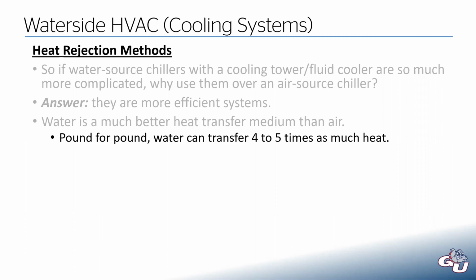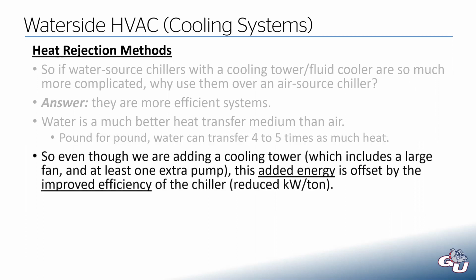Pound for pound, it's about 4 to 5 times as much heat that you can transfer through water as opposed to through air. So we're adding this cooling tower, and that tower has a big fan on it, at least one extra pump, most likely 2 extra pumps. That added energy for those systems is offset by improved efficiency of the chiller. So we have a reduced kilowatts per ton at the chiller, but we are adding energy at the cooling tower and some additional pumps. But ultimately, it works out that these are more efficient systems in the end.